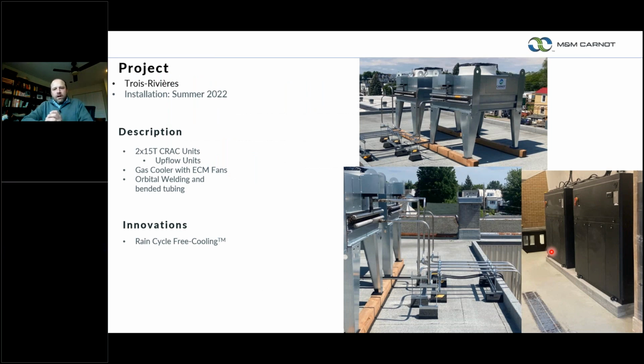Just a quick introduction of what our equipment looks like. It's fairly similar to what you would see in any perimeter style cooling system. These two units happen to be 15-ton upflow units connected to each gas cooler. Our 15-ton machine is a single circuit machine where we just have this on the right, our indoor unit hooked up to our gas coolers that are located on the roof.